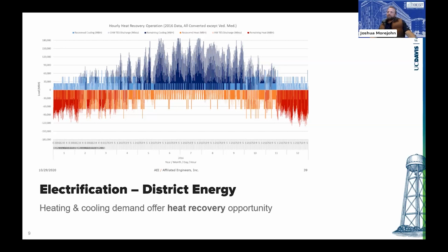The additional benefit is that with a hot water system, you can do things to meet that additional heating load where you can't recover the cooling. There's not enough cooling going on in the buildings in the winter to meet your full heating demand. That's where the red is shown. That heating load could still be met with the heat recovery chillers if we can find another low temperature source for our chilled water to get it up to 60 degrees. So what we're planning right now is a geo-exchange system where we would pump the water down into the ground into closed loop geo-exchange just to get the chilled water back up to 60 degrees and be able to run our heat recovery chillers in the winter to meet our winter load as well.